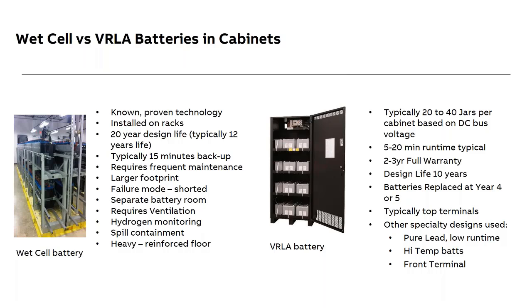But a lead acid, a VRLA battery, cannot really be designed for less than 5 minutes because of a coup de fouet. It cannot take a load step just off the cuff. Pure lead handles that better, and pure lead batteries also can be designed to lower run times. They handle temperature better, where standard VRLAs are very sensitive to temperature.